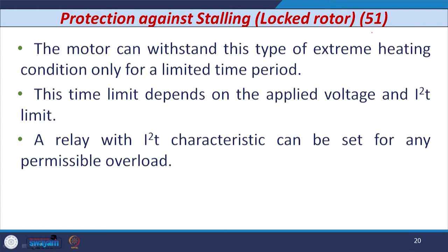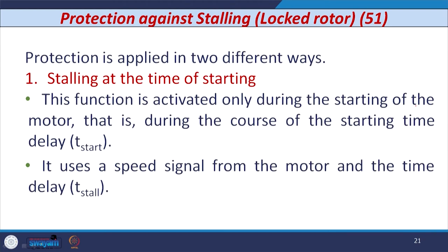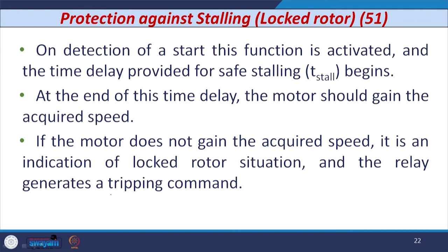The motor can withstand this extreme heating condition only for a limited time period. This time limit depends on the applied voltage and the I²t limit, where I² is the current flowing through the winding and t is the time. A relay with I²t characteristic can be set for any permissible overload. Stalling protection is applied in two ways. The first stalling protection is given at the time of starting of the induction motor — this function is activated only during starting, during the course of starting time delay T_start. It uses a speed signal from the motor and the time delay T_stall, which is the stalling time specified by the manufacturer.